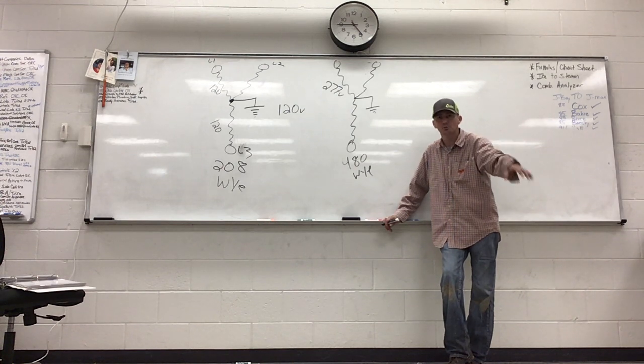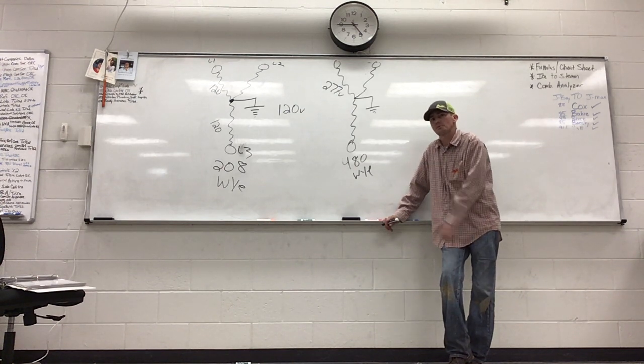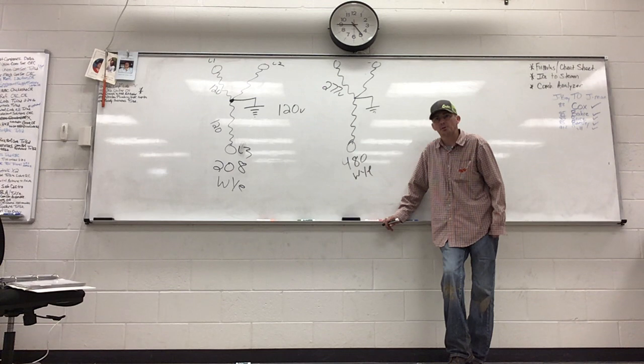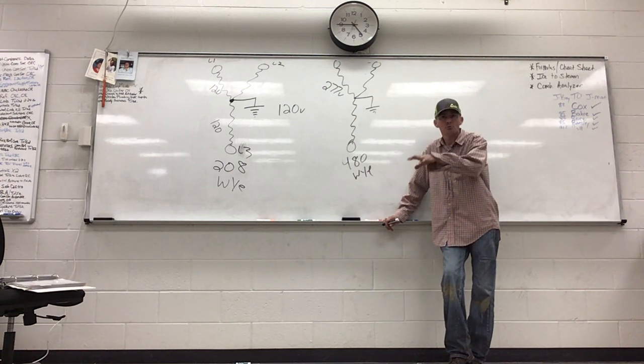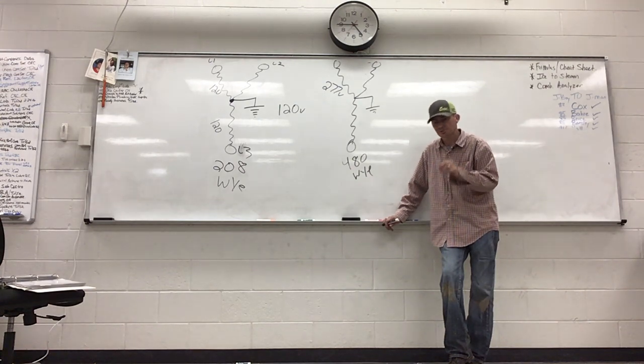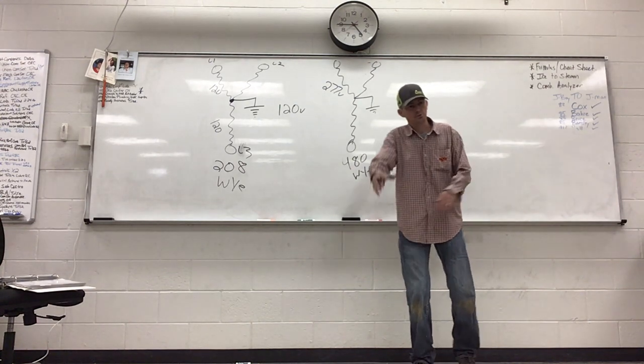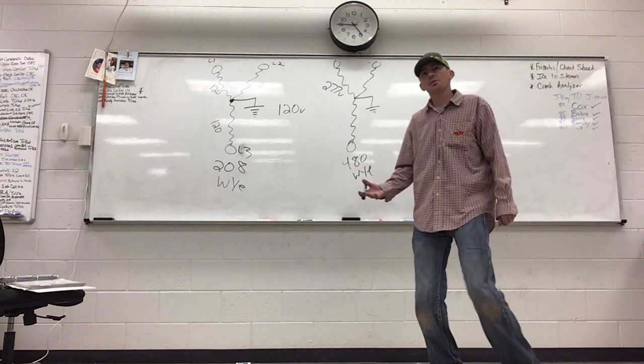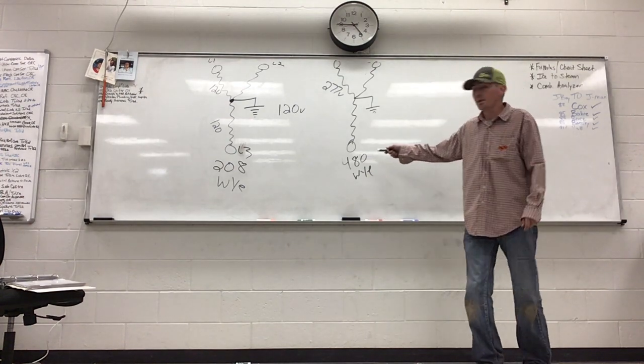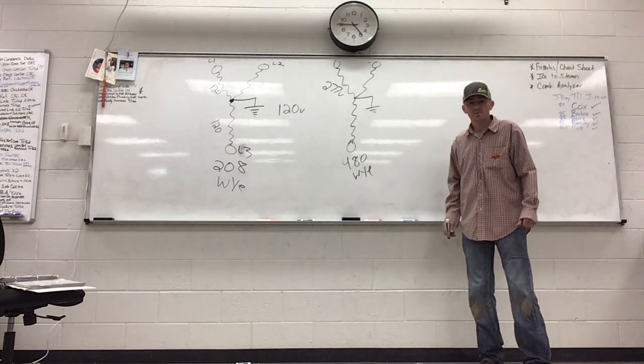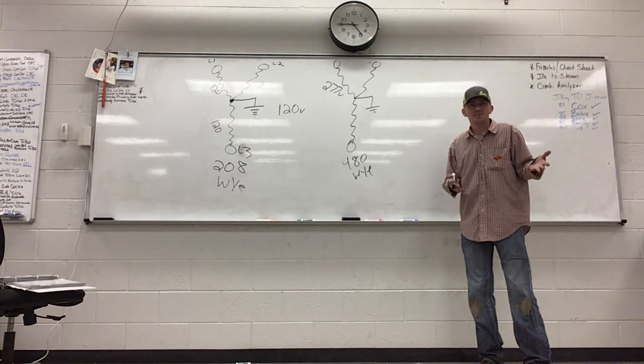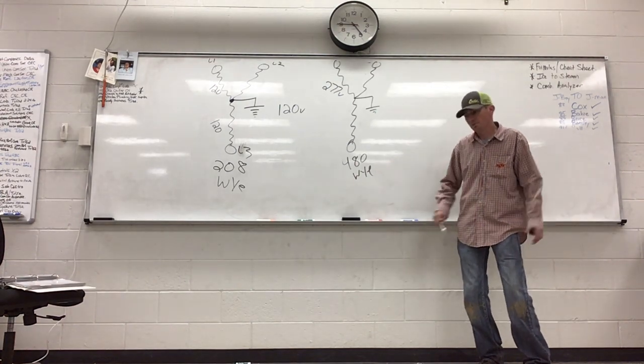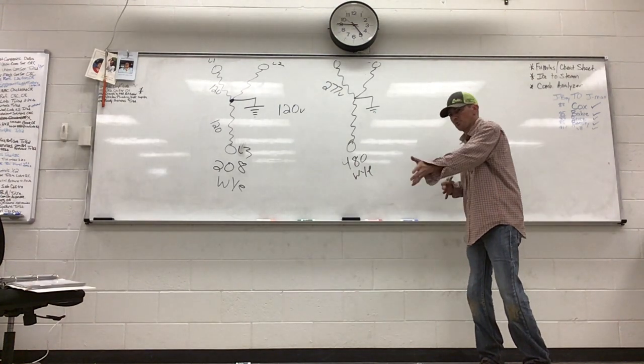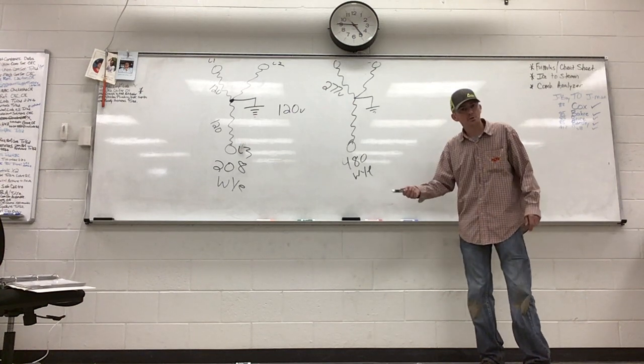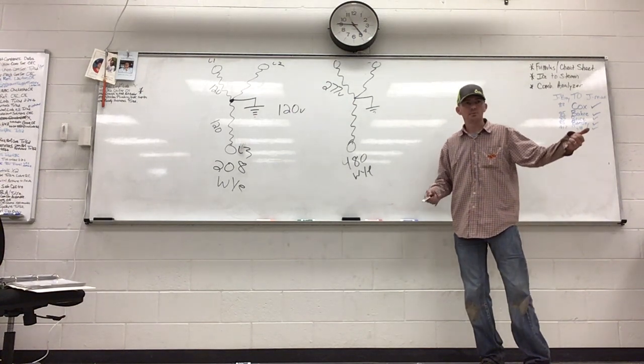Usually they're in the mechanical rooms, right? I can run you guys over to the Reynolds building and look over there, it's 480, or the Noble Center, or whatever. As we go into each mechanical room, you'll see a standalone transformer, several kVA transformer. All that does is take this voltage and knock it down to 120. So anytime we have a 480 volt building, most of the time we have to set additional transformers just to get 120 volts to power our plugs and stuff, right?